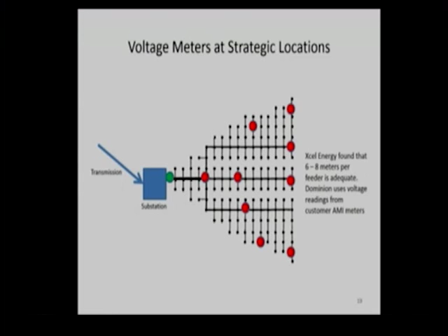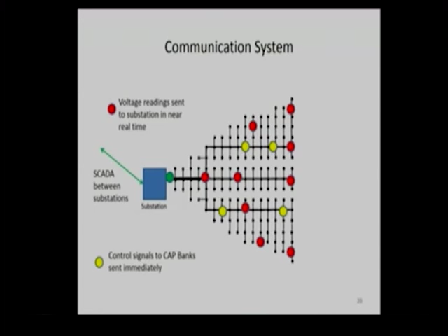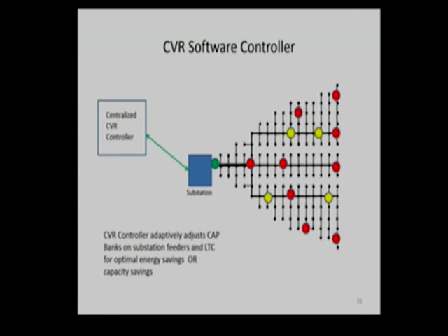You then need a communication system to get the readings back to the substation. Substations already communicate with central utility locations through the SCADA transmission system, but we need communications that work out in the grid itself. We also need then the software at a controller, and that could either be in a substation, it could be at a central location and talk to the substations, or pretty much at any location. So this CVR controller will adaptively adjust the capacitor banks on the substation feeders and the load tap changers for optimal energy savings.